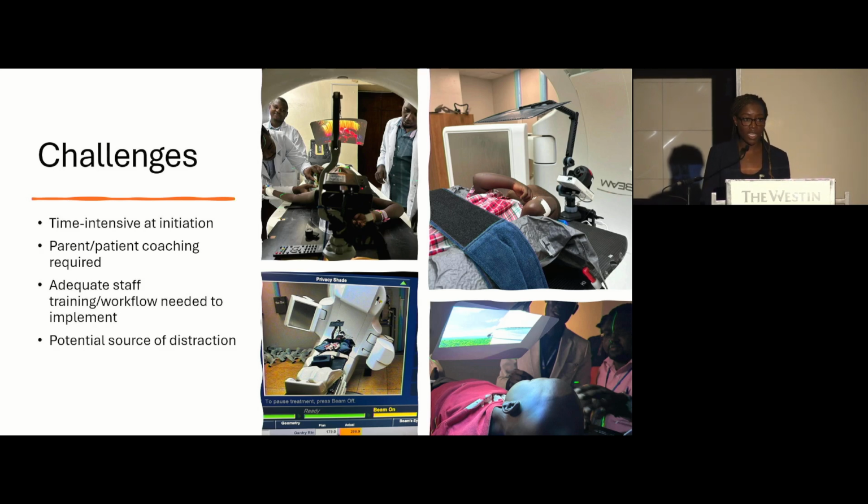Again, adequate staff training. We've been doing in-person training, so when we deploy a device, we usually will send a team out there just to train the staff and deal with any issues that come up. And then as I learned this week, when it works really well, it can actually create quite a bit of distraction. So this is a 2-year-old. This was her first fraction without sedation, and this was in Uganda. And she was so excited watching My Little Pony. She started trying to touch the ponies on the screen, and this is where coaching comes into play. Thankfully, we were treating the abdomen, and we were far from the head and neck region, but just coaching patients and parents about sitting still and avoiding any type of interaction with the device while they were being treated.